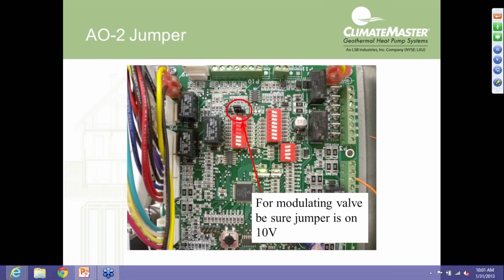Now, right below dip switch bank number 2 here, that is that AO2 jumper. Just a few minutes ago when I was talking about these jumpers on the board here, this AO2 jumper is very critical to our VFlow components, whether it be the modulating valve or the variable speed pump. If it's in the incorrect position, that pump or that valve will not be operating properly, and it's probably going to lead to some lockouts for you. So it's very important that this jumper be in the correct position.